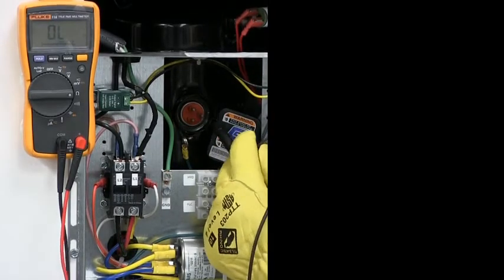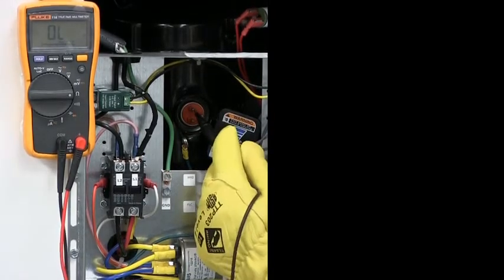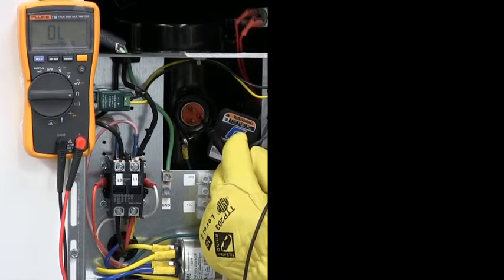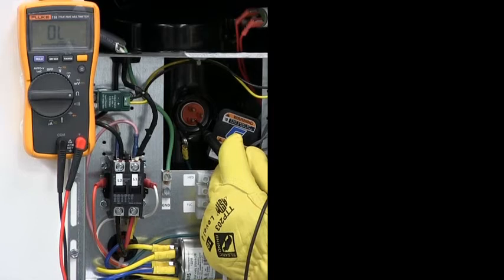As you can see, there are three pins here. The top one is common, the one on the right is start, the start winding, and the one on the left here towards the bottom is your run.